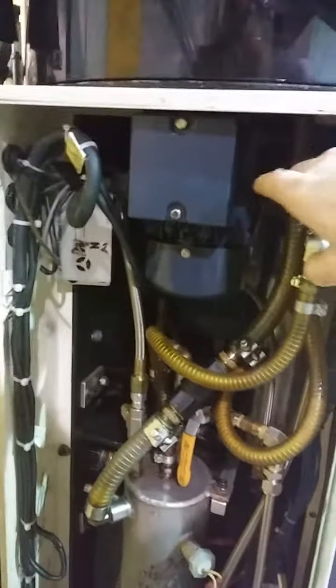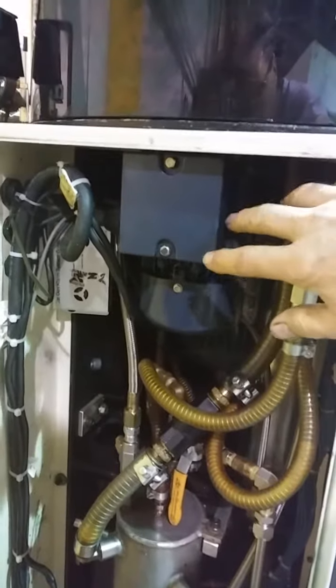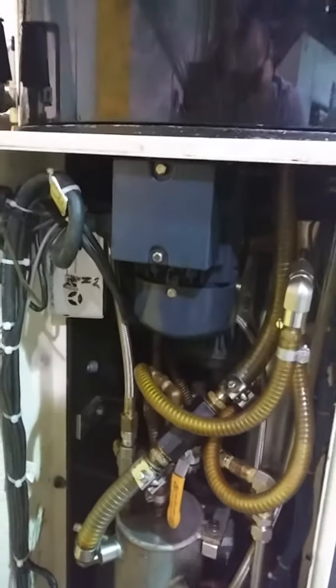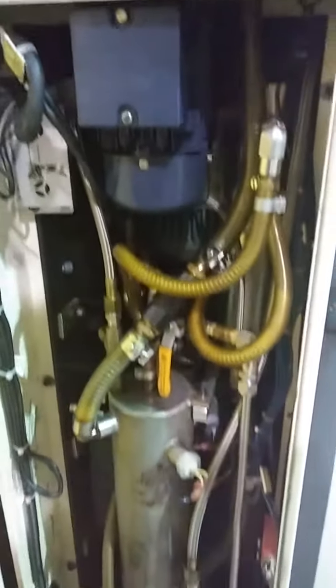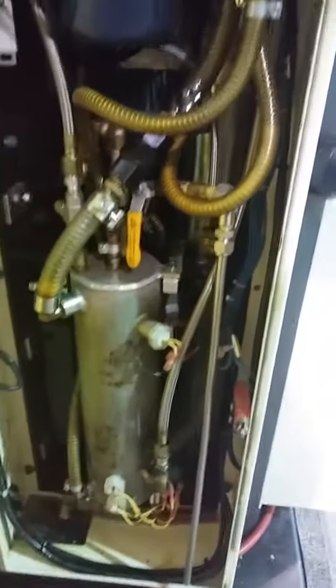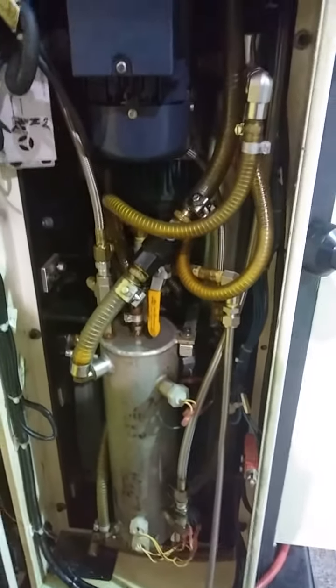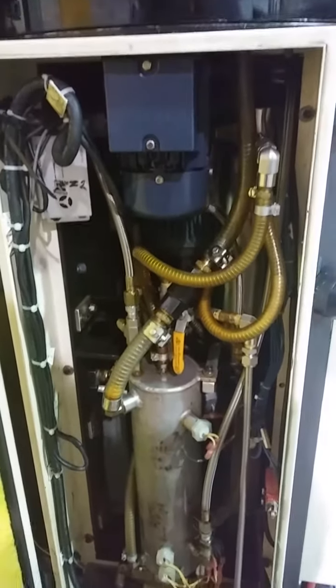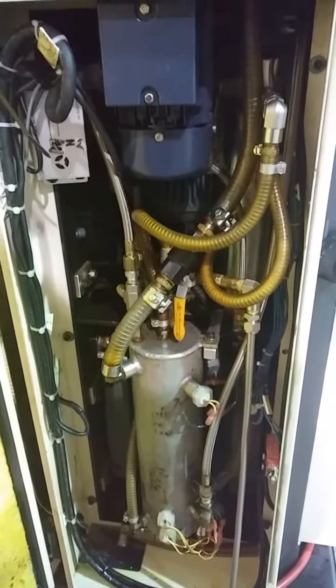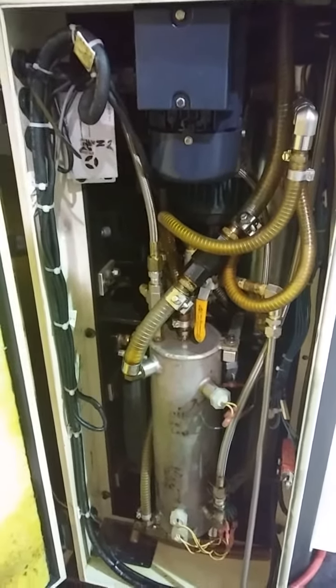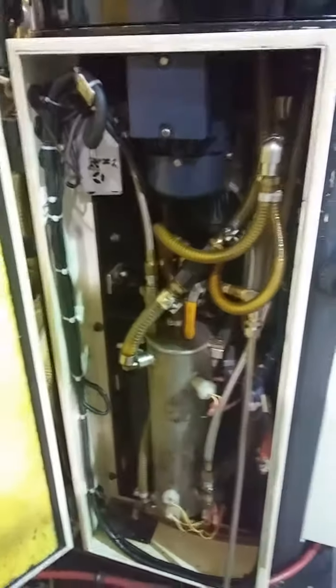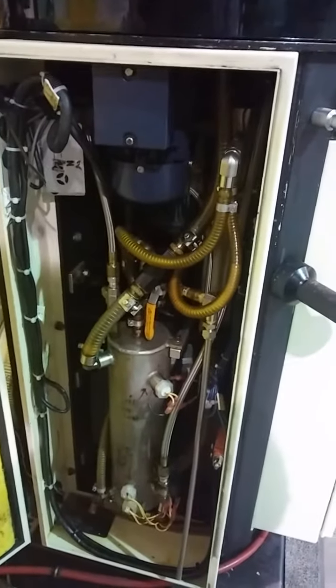And this is a 1/4 horsepower motor for the oil pump. And inside here there's a fan, a high velocity fan, 3800 CFM, that runs and generates a pressure inside the cabinet, lower cabinet, to dilute any gases and force it up through the top of the machine and out the chimney going out there.